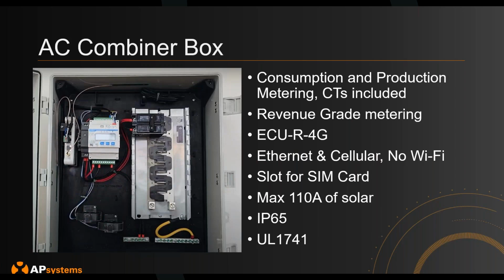I'd say it's not required. The AC combiner box is not a required product for every APsystems install. So if you don't want CT monitoring, you don't have to use this box—you can just do what you'd normally do, purchase an ECU-R, bring the solar in, and use a generic load center for your breakers. The purpose of this box isn't to require you to use it, but to offer it as a solution if you have a customer who wants consumption monitoring, making it easier for you to install. So again, it's not required, but it can be helpful for customers who want those consumption measurements.